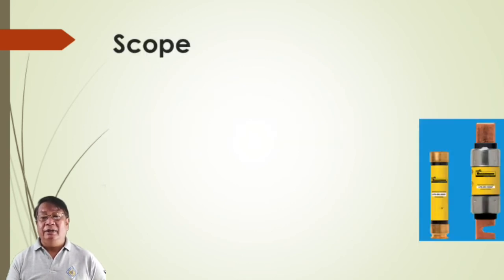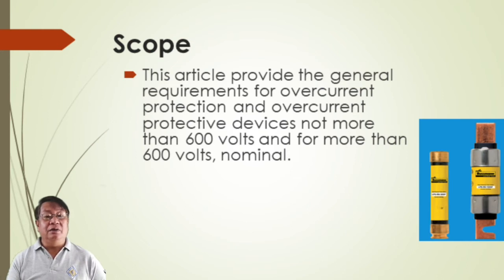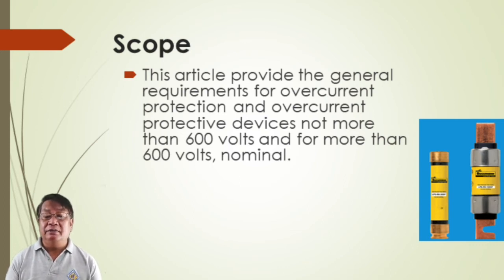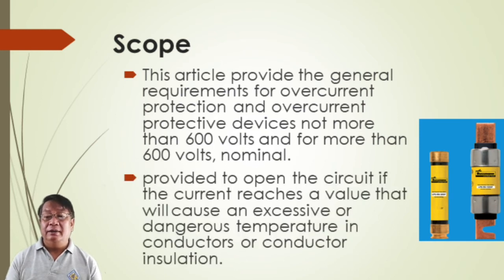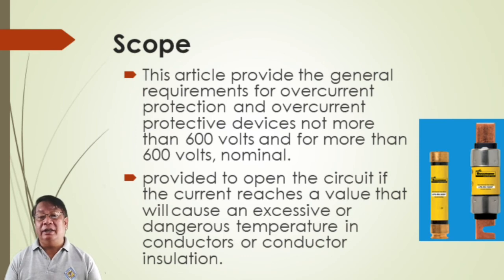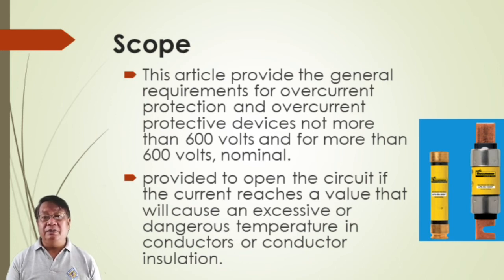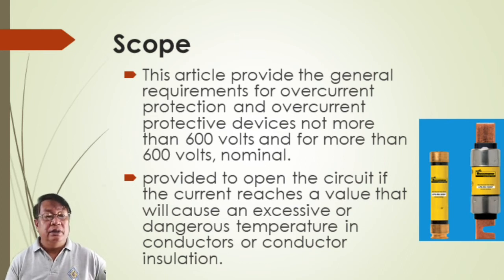Article 240 covers overcurrent protection. The scope provides general requirements for overcurrent protection and overcurrent protective devices for not more than 600 volts and for more than 600 volts nominal. These are provided to open the circuit if the current reaches a value that will cause an excessive or dangerous temperature in conductors or conductor insulation — protecting conductors and any other load in the system.